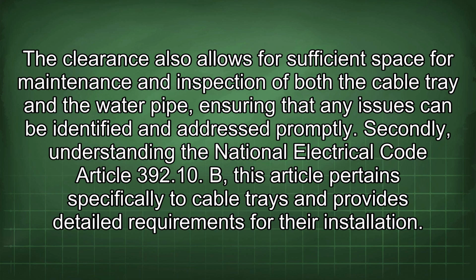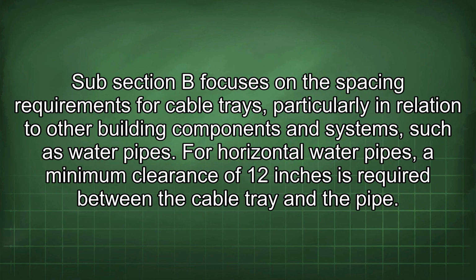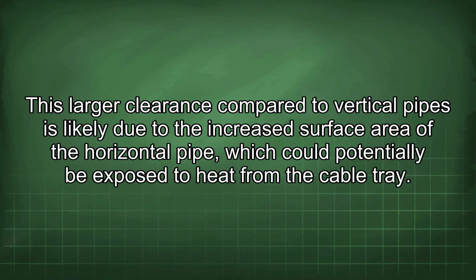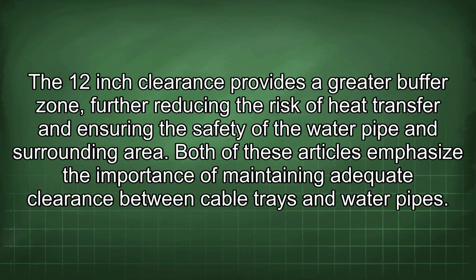Secondly, understanding the National Electrical Code Article 392.10 B. This article pertains specifically to cable trays and provides detailed requirements for their installation. Subsection B focuses on the spacing requirements for cable trays, particularly in relation to other building components and systems, such as water pipes. For horizontal water pipes, a minimum clearance of 12 inches is required between the cable tray and the pipe. This larger clearance compared to vertical pipes is likely due to the increased surface area of the horizontal pipe, which could potentially be exposed to heat from the cable tray. The 12-inch clearance provides a greater buffer zone, further reducing the risk of heat transfer and ensuring the safety of the water pipe and surrounding area.